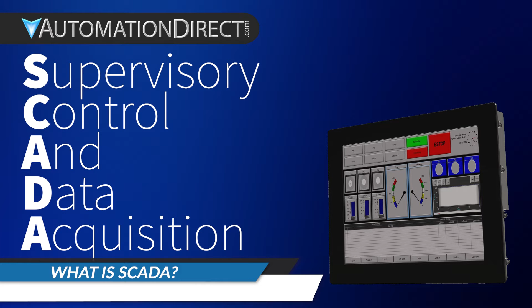SCADA stands for Supervisory Control and Data Acquisition, and that name spells it out. It's not a single device, it's a system. A SCADA system pulls together data from across an entire plant or process, supervises what's happening, logs information, and may even issue control instructions across multiple areas. It sits at the top level of the automation hierarchy, making certain each piece of the system is doing its part.